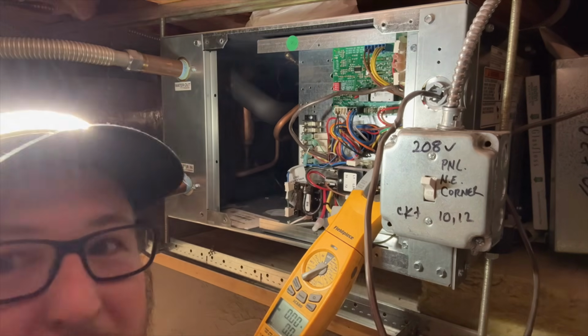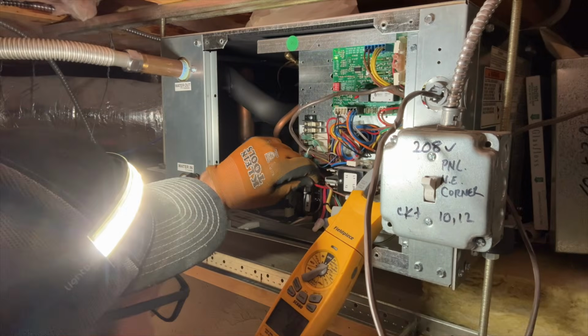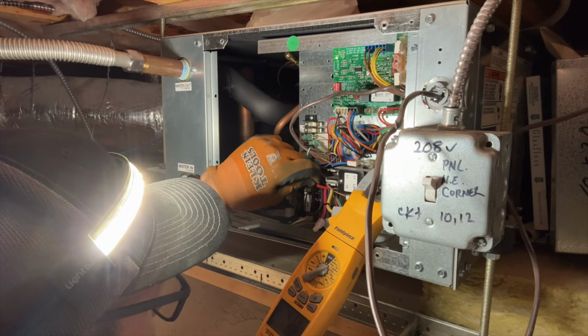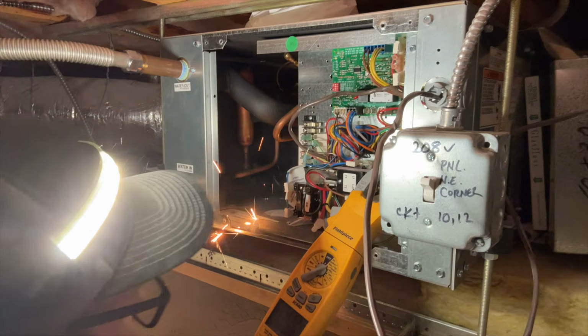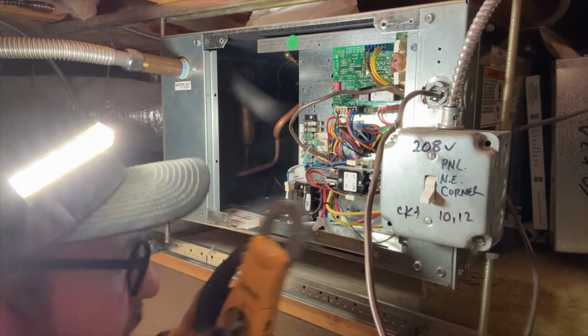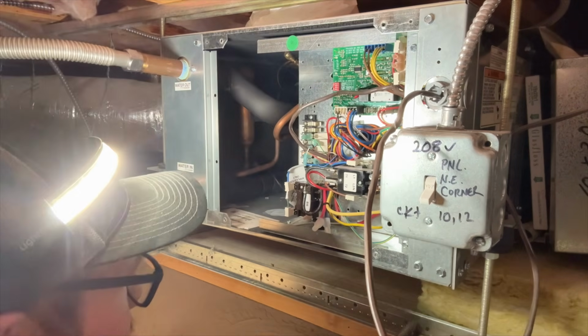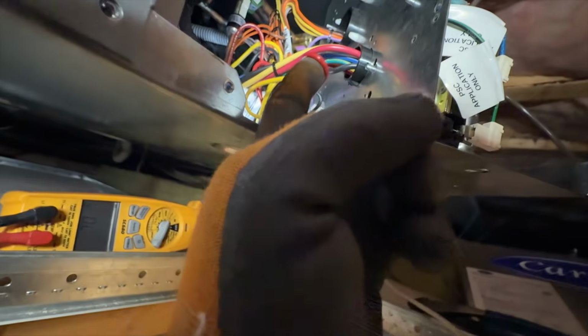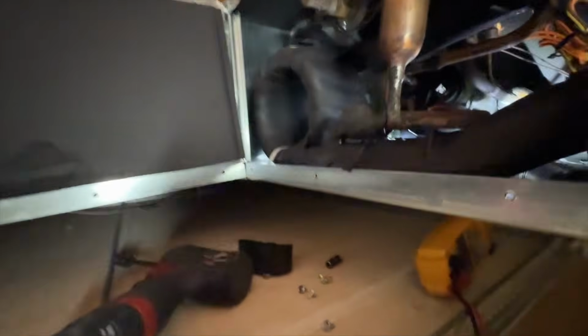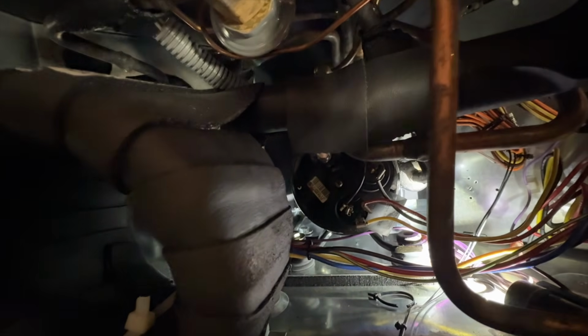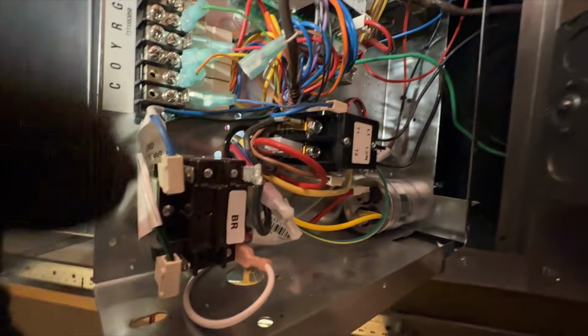Well, there's our short. Now we got to see what it was. Well, I haven't found the source of the short, but it looks like this is where it arced. It was right here at the bottom of this panel. I'm not seeing any damage on the wires anywhere. I don't know. And then I have the terminal opened up for the compressor, and it looks fine. And I can't find any damage in the wires. So I'm gonna keep looking, but yeah.